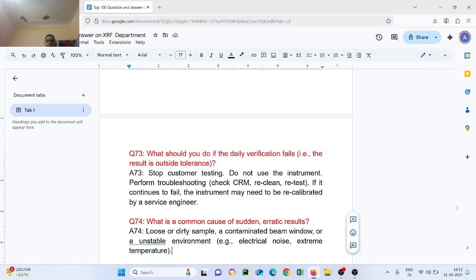What is the common cause of sudden erratic results? Loose or dirty sample, or a contaminated beam window, or unstable environment. Example: electrical noise, extreme temperature.